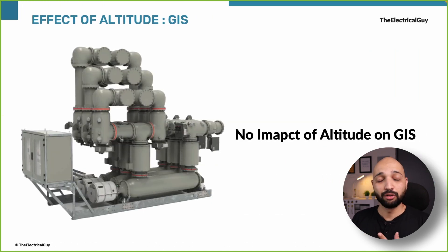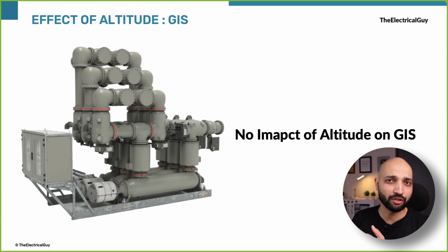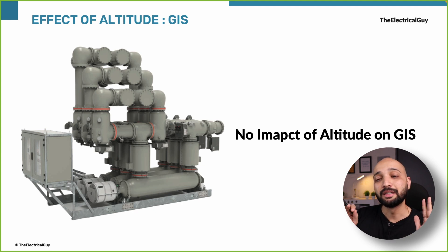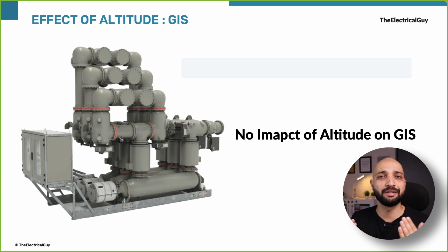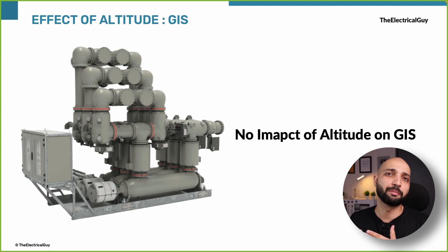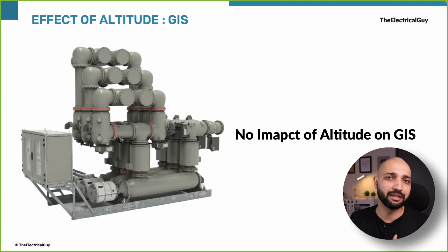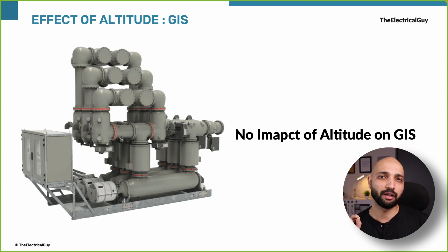Do we use air in GIS for insulation? The answer is no. So does altitude matter in case of GIS? Again, the answer is no. GIS has no impact from altitude because everything is insulated by SF6 gas — phase-to-phase and phase-to-ground insulation are both given by SF6 gas, and it is completely encapsulated. However, if outdoor bushings are used, those bushings need to be considered for higher altitude levels.